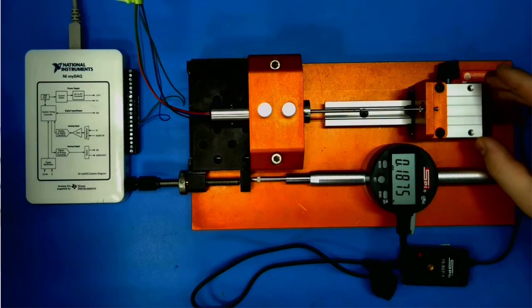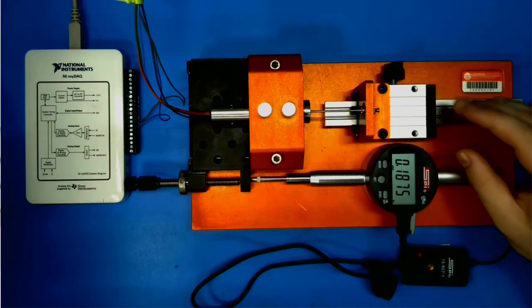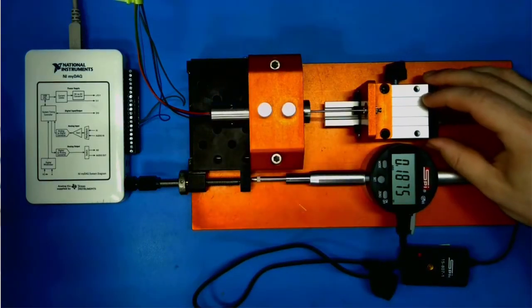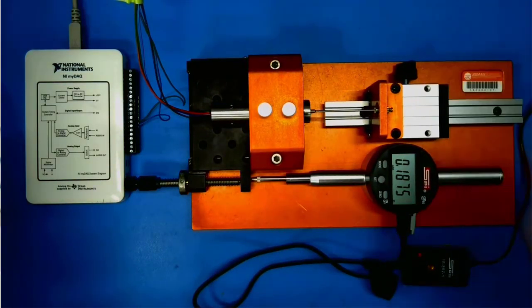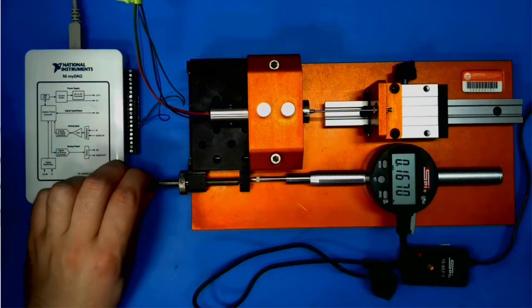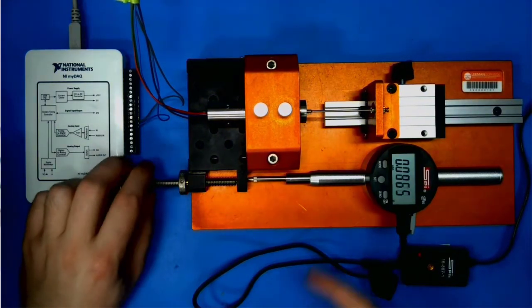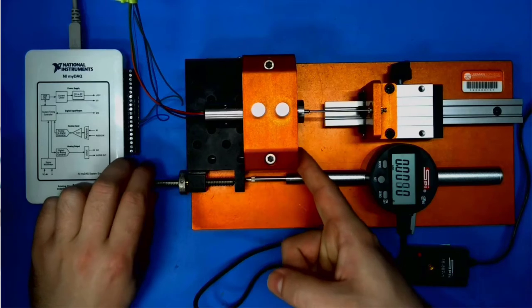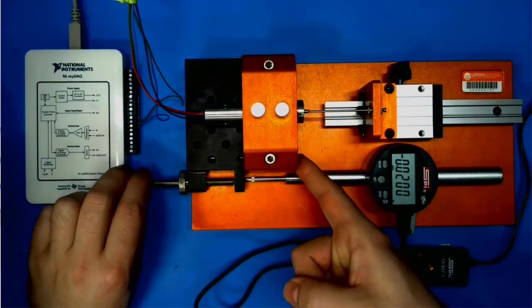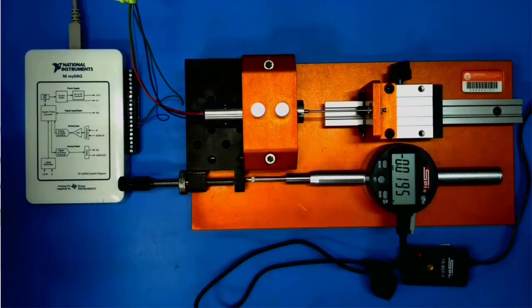Now you're going to move the carriage so that the core goes into the DCDT, and once that's aligned, tighten the core nuts. Leave the carriage free for the moment. Using the adjustment screw on the stage, move the stage so that it is centered and the edges of the stage are flush. Zero the gauge by pressing the 0 button. Now go ahead and apply power to your transducer.